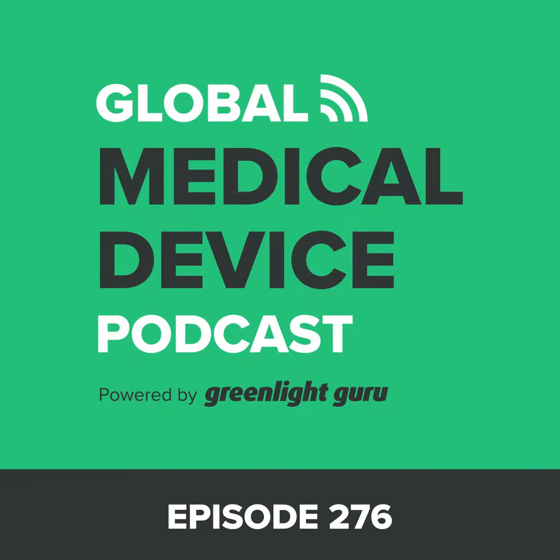And then there's a subset of products that are reprocessed and reused. They need to have direct marking, and that can be a technical challenge. Sometimes you have to go back and redesign your manufacturing process. Some companies engage a laser etching or chemical etching or something. But anyway, it takes a design effort in many cases, and then testing to see if everything is still safe and effective after applying that particular mark.